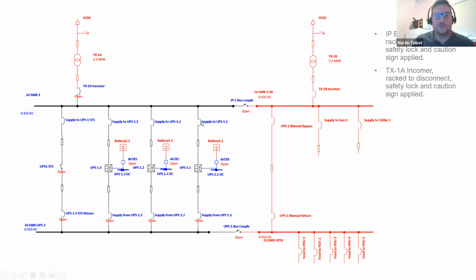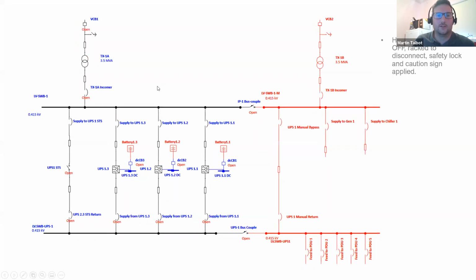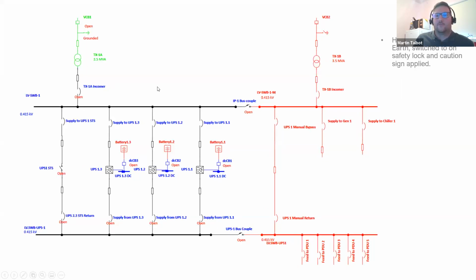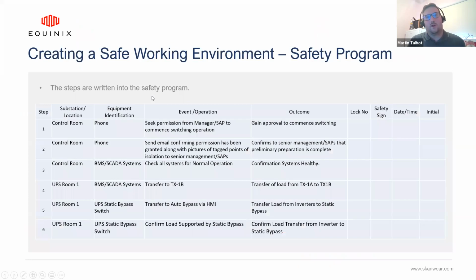Then we can disconnect the switchboard, shut down the UPSs correctly, open up the transformer incomers, and make sure that we're fully disconnected, and the bus coupler at this stage. However, because again, as Marcin said, there's the line side and the load side, we want to make sure this side is also isolated. So we have to isolate at MV on the transformer side as well. Okay, and then it's earthed. So all of these steps are what we want to do to safely isolate our switchboard.